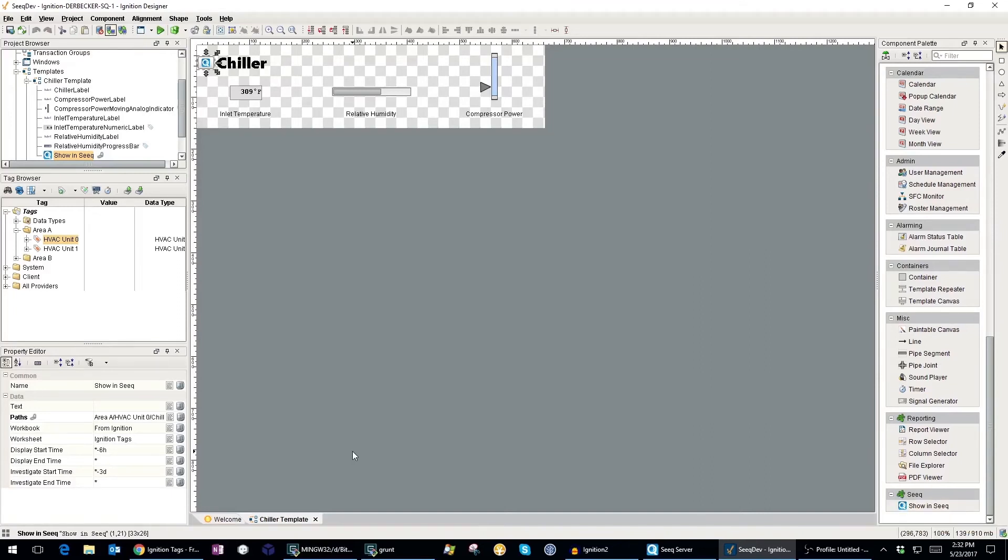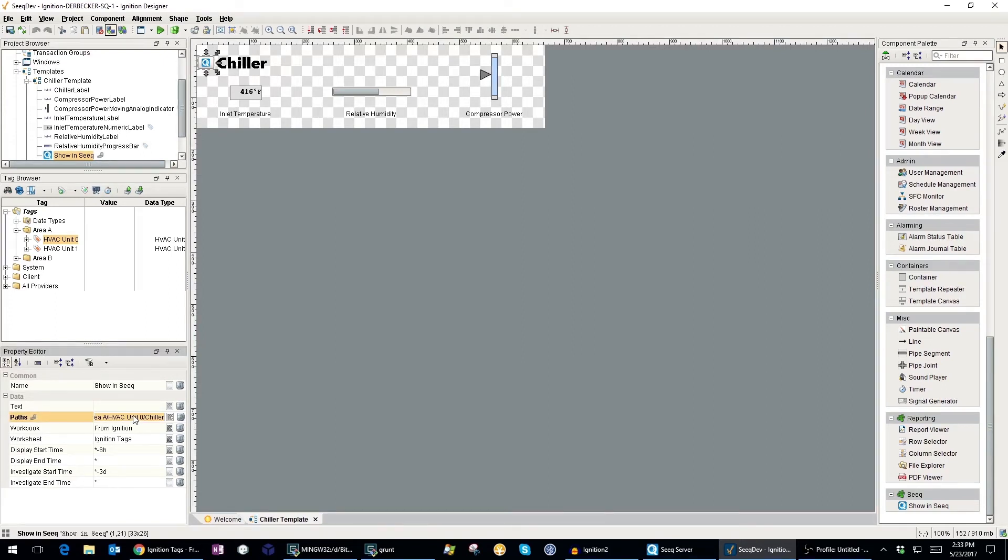I can configure the button with a few key properties. The paths property dictates which tags will be shown in Seeq when the button is clicked. Since I'm using this button on a template, I'm taking advantage of Ignition's property binding features to dynamically specify the tag path using an expression.